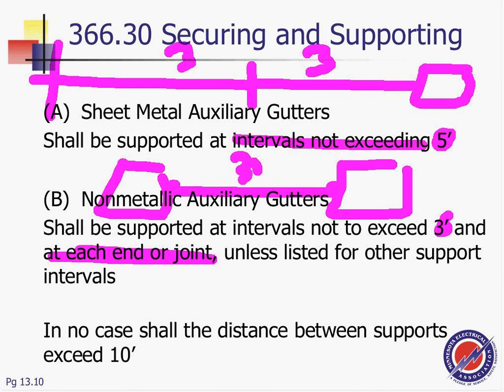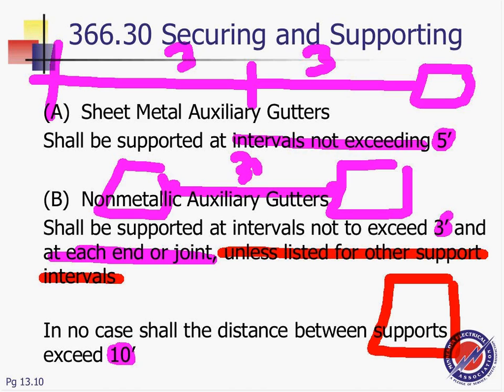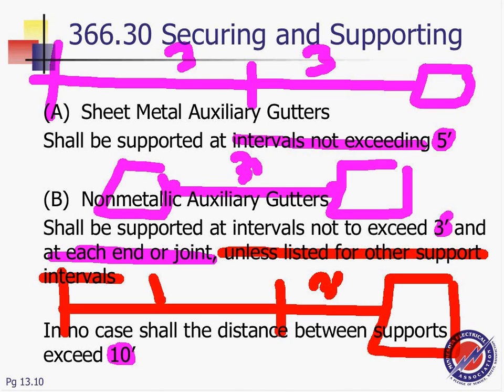In no case shall the distance between supports be more than 10 feet, unless listed. And here, this is where it confuses you guys on the quiz. It's 3 feet, but they have this tiny little exception, unless listed for other supports. So if the non-metallic wireway is listed for use, you're going to support it every 3 feet from equipment, and I'm going to go all the way up to 10 feet only if it's listed, no more than 10 feet. Only if it's listed. I emphasize the word only if it's listed. Any questions, guys? Any questions about supporting that baby?